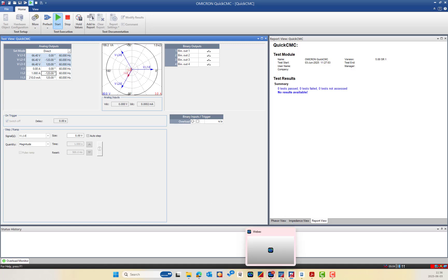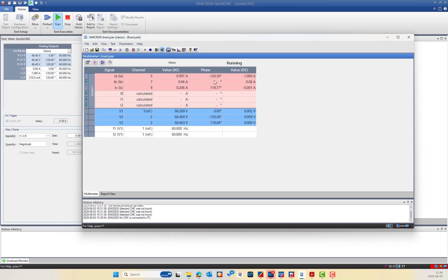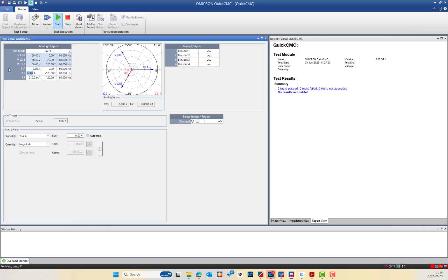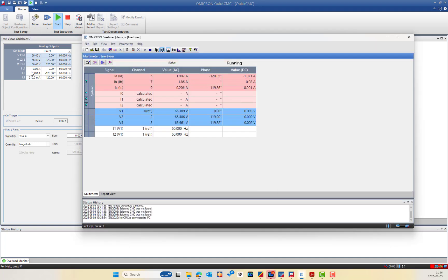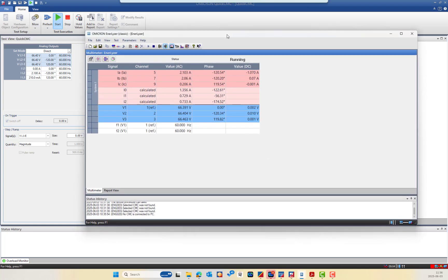At 1A, the clamp meter is still detecting the phase angle measurement. The C-Shunt shows the same weak signal at 1.9A. But at 2.1A, both of them indicate the phase angle correctly, because we exceed 2% of the 100A nominal range — that is, 2A. So the C-Shunt 1 milli-ohm is also now able to measure the phase angle with no weak signal.